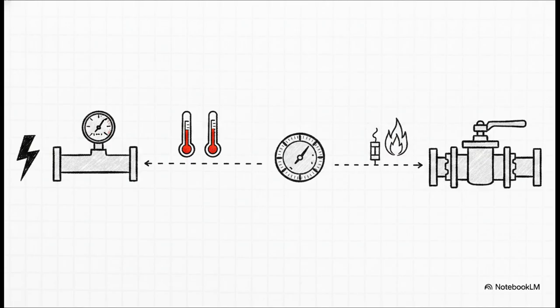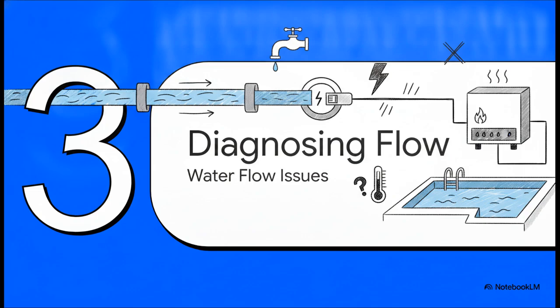Here is the exact, unchangeable sequence of those safety gates. We have the pressure switch, the high limit switches, the thermostat, the thermal fuse, and finally, the gas valve. To troubleshoot a dead heater, we simply follow the power down this exact path to find exactly where the voltage stops. It's really like solving a puzzle. Which brings us to Section 3, diagnosing water flow issues.